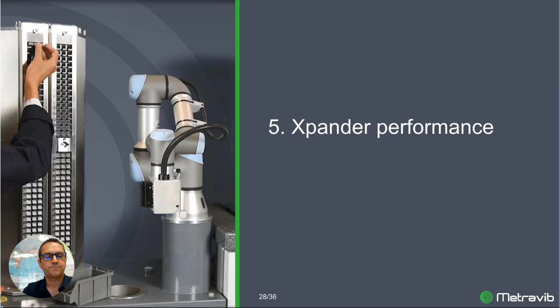The first test here corresponds to 50 consecutive tests at room temperature. The goal is to express the DMA measurement intrinsic repeatability, and you can see that the standard deviation we get on the stiffness we measure is roughly 0.01%, and on tangent delta 0.28%. In this case, the specimen is a metallic specimen with a middle range stiffness, and that already gives a very good idea of the performance of the system.